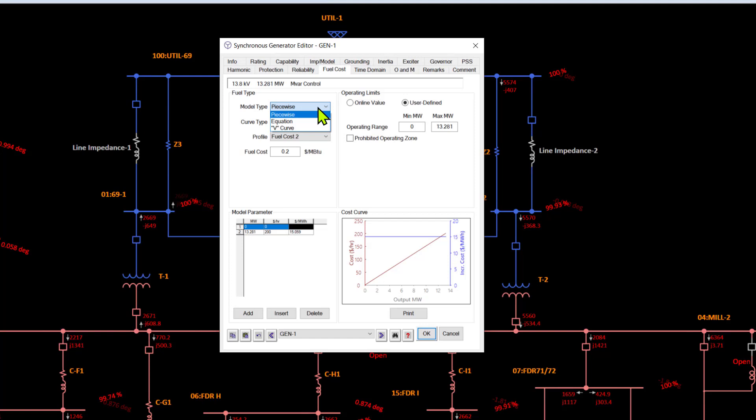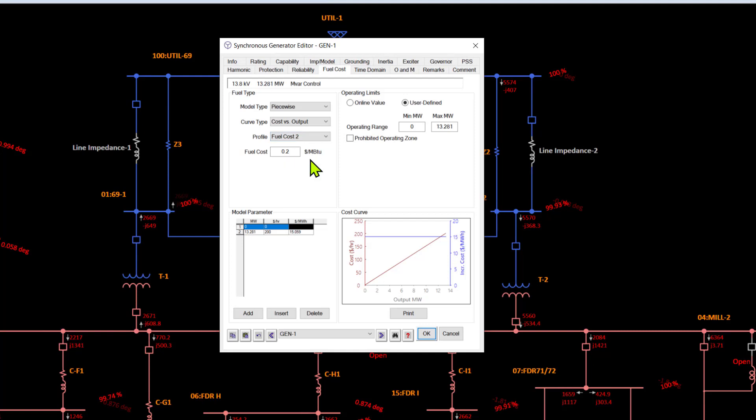The fuel type can be established based on a piecewise, which is point-wise equation, or V-curve based. You can also define fuel cost profiles which ETAP allows you to define about 10 of them. This lets you manage not just one fuel price but multiple fuel prices, especially if your generator is capable of running on more than one fuel type. You can decide what the fuel type mix should be by entering the blended cost or the individual cost of the fuel.